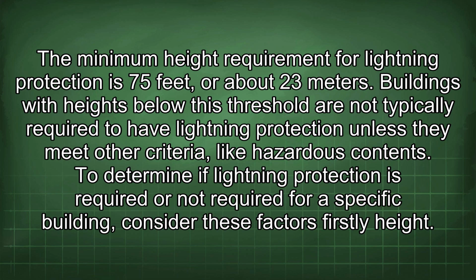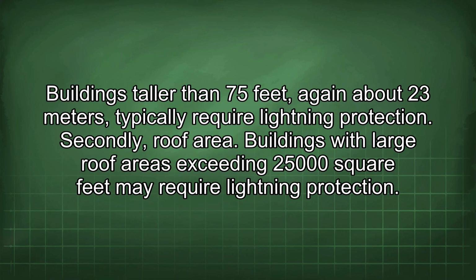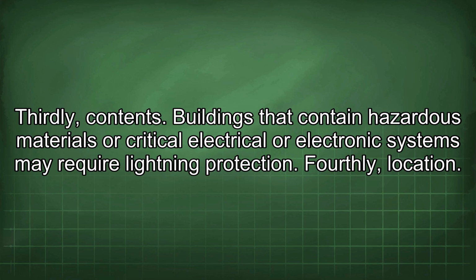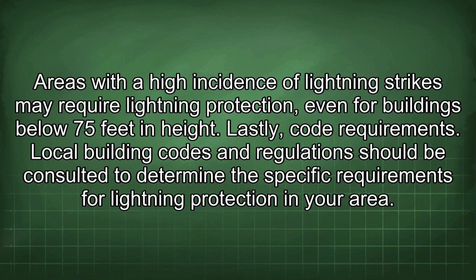Firstly, height. Buildings taller than 75 feet, again about 23 meters, typically require lightning protection. Secondly, roof area. Buildings with large roof areas exceeding 25,000 square feet may require lightning protection. Thirdly, contents. Buildings that contain hazardous materials or critical electrical or electronic systems may require lightning protection. Fourthly, location. Areas with a high incidence of lightning strikes may require lightning protection, even for buildings below 75 feet in height. Lastly, code requirements.